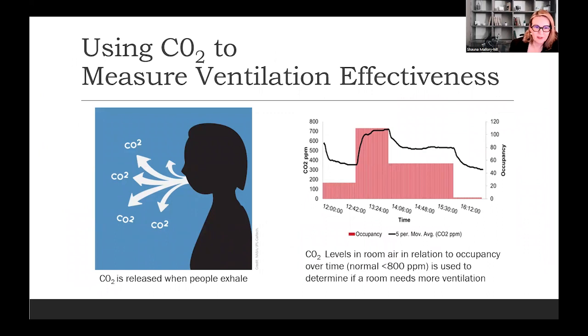I just wanted to also talk about CO2 measurement, just so we understand what it is. CO2 is released when people exhale. When we're doing performance measurements, we use it as a proxy for all sorts of ventilation effectiveness. But when we talk about COVID, COVID is something we exhale, so it's a very good proxy for airborne viruses. When we measure CO2 levels, it's not generally a spot measurement. We measure it over time, and in relation to outdoor air. Outdoor air is normally at 400 parts per million, so I look for amounts that are at least twice that, over 800 parts per million. And generally, if it's over 1100 to 1500, then the system needs some looking into. So just some notes about that.